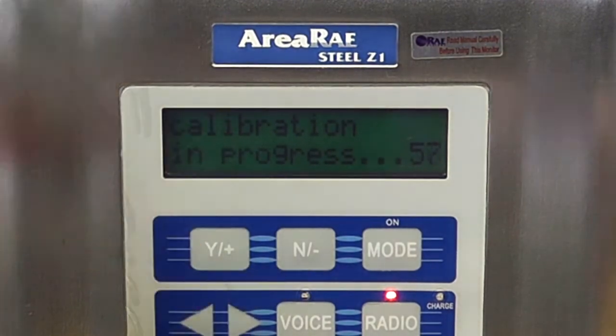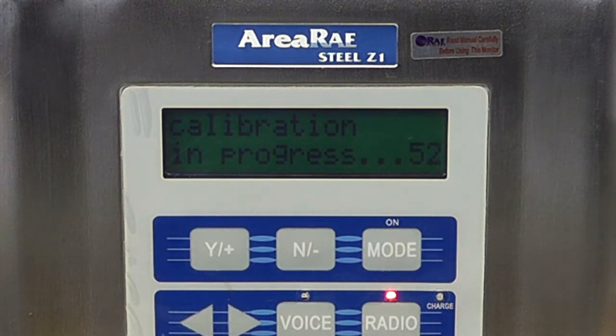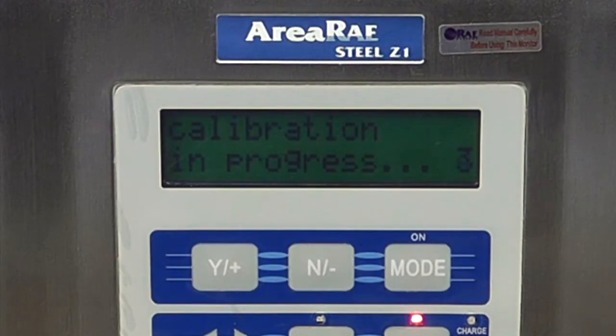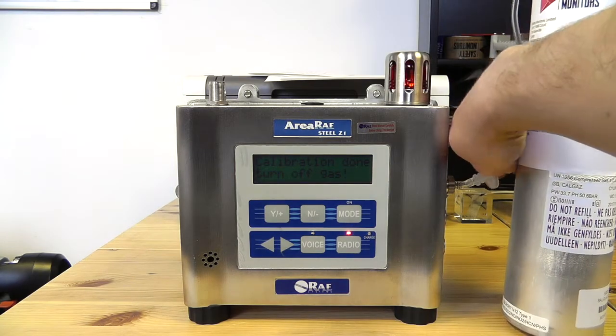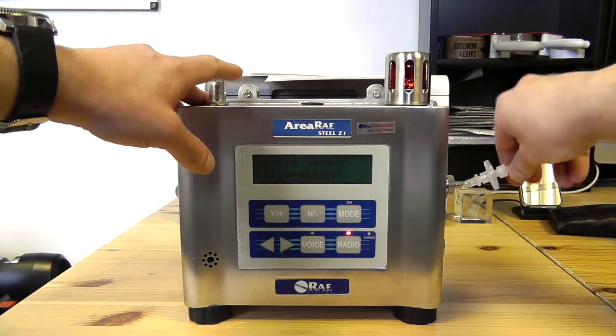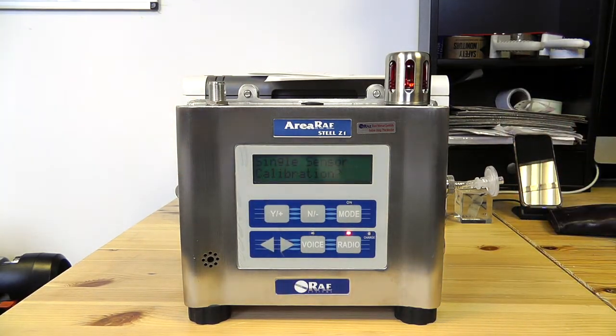we have now done. We're using an on-demand regulator on one of our cans of gas, and then it will do a multi-sensor span calibration, which takes around 60 seconds. So we can see the calibration has been successful, and it gives us a reading on each of our sensors. We can see everything is reading as it should be. We can now turn the gas off, so remove this gas from the unit, and then we can perform a single sensor user calibration on the isobutylene.